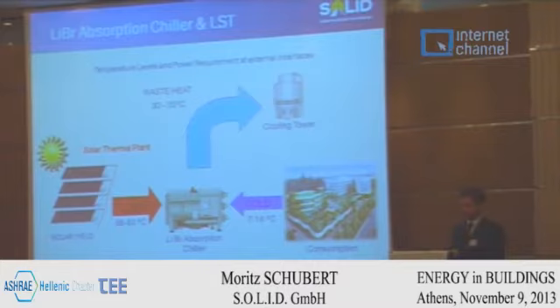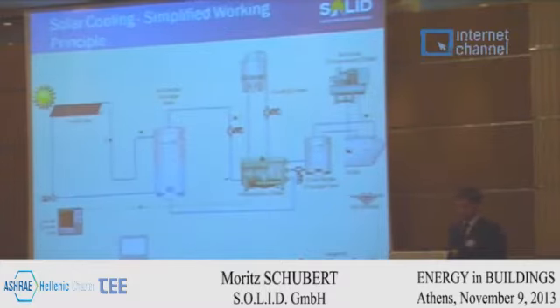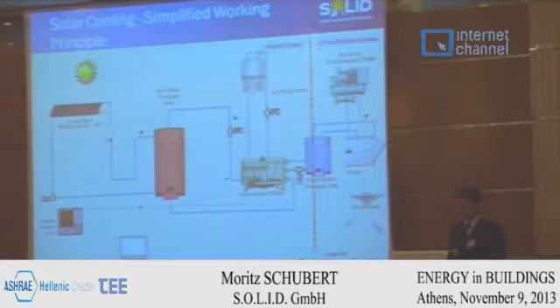For the cooling towers, we normally require wet cooling towers, because the lithium bromide absorption chiller normally demands a return temperature between 28 and 30 degrees, which is then heated up inside the chiller to 35 degrees. Yes, this is another simplified working principle, as I showed you before, with the absorption chiller and so on. Here we can see the boundary between the solar cooling system and the conventional cooling system.